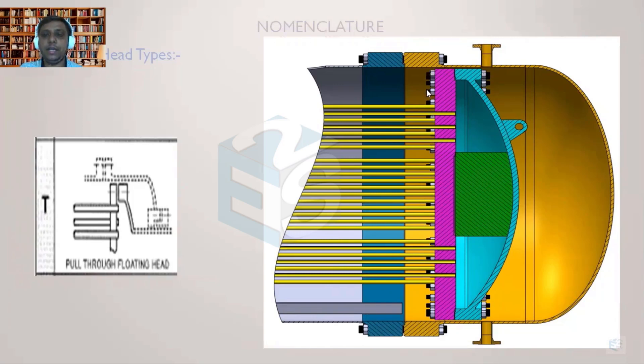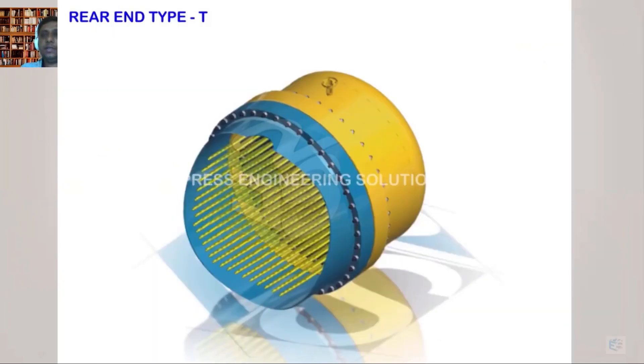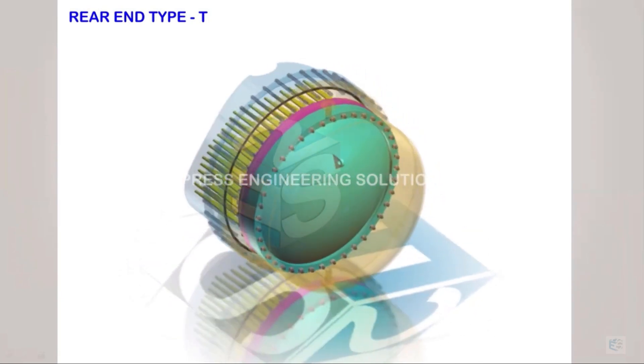The disadvantage is that the gap is much more, the shell ID has to be increased, and since the flange ID is increased, the flange thickness will also be on the higher side. This entire head assembly can be removed from the other side, causing higher shell diameter and hence higher cost compared to the S-type. This is the pull-through type of floating head — it is also called an internal type of floating head like the S-type, but it is pull-through and has no backing device.